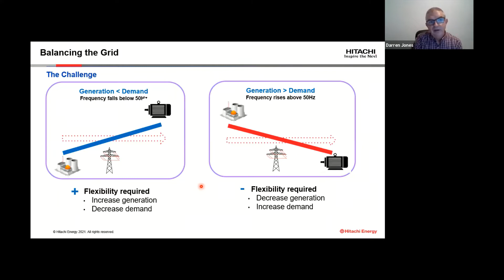Once that frequency began to fall, that led to the operation of low frequency demand disconnect schemes on the connected distribution systems. I know UK Power Networks had quite a significant amount of their demand disconnected from the network at that time. That was demand disconnection to make sure that the balance could be brought back to the available generation. The ultimate risk is a cascade failure and a widespread system blackout. So the system worked perfectly at that time, and the balance was maintained. Even though some people were off supply, which of course is not the best experience, they managed to keep system stability and keep the network online. So that's the job that needs to happen: balancing the grid between generation and demand.